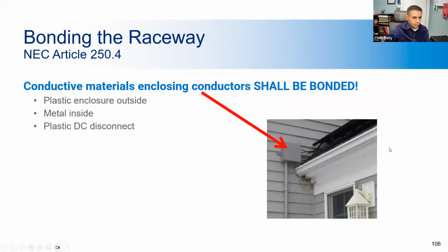So here, we saw an example of this earlier. If you have a metal conduit that's between two non-metallic enclosures, within this enclosure, you would want to have the conduit bonded. And in this case, this is a metallic enclosure on the inside, and not metallic on the outside. So you want to have a ground bus or a grounding wedge that has to be installed inside the enclosure to properly ground it and bond it.